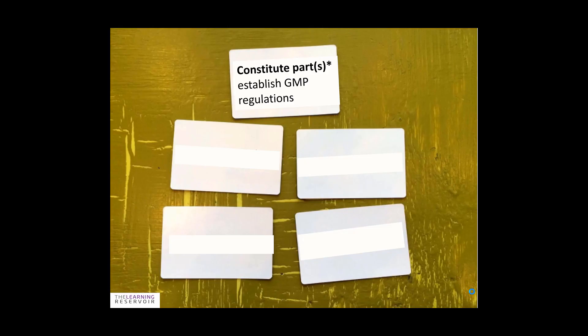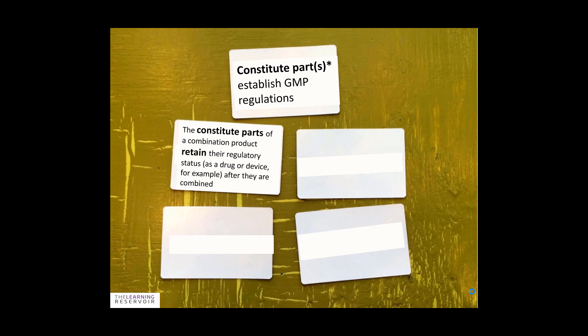The constituent part of the combination product establishes the GMP regulations. Even though it is a combination product, we must know what combinations made up that product — what are the constituent parts that went into it. The constituent parts of a combination retain their regulatory status as a drug or device after they are combined.